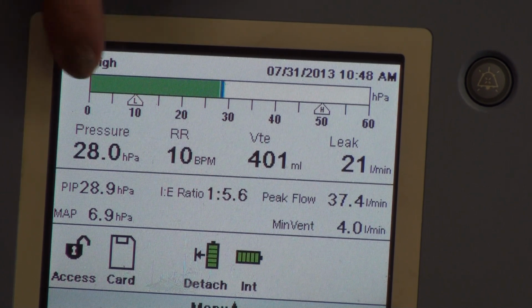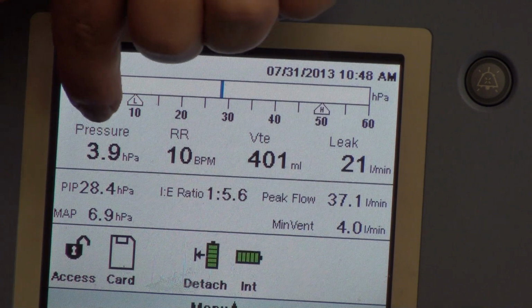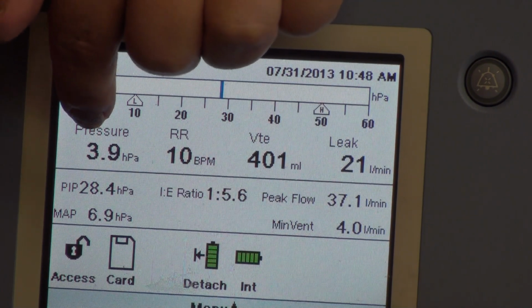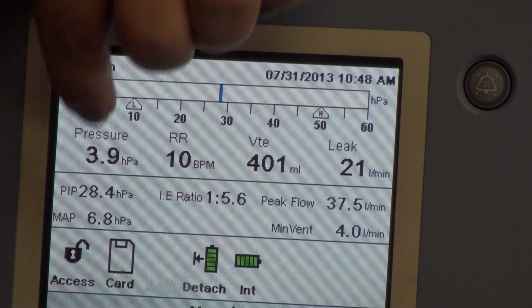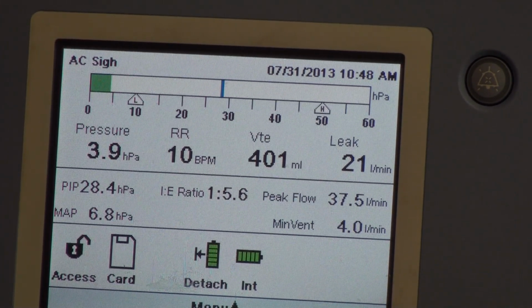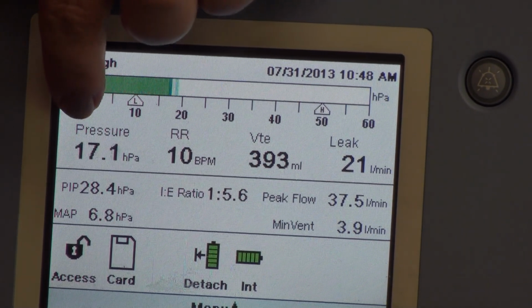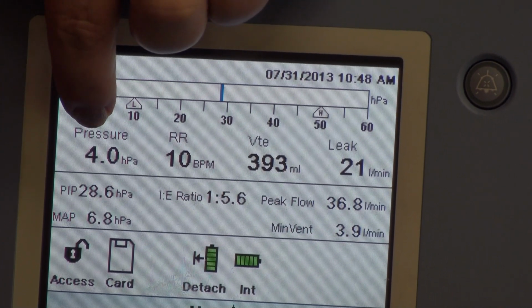I is going to be your current patient pressure. In other words, from where it starts, it starts at 3.9, so you must have a PEEP of 4 sitting in there. And it goes all the way up till it delivers the breath, comes all the way back down. It's showing every little piece as it's happening, the pressure that's going in, the pressure that's going back out, and where it sits at.